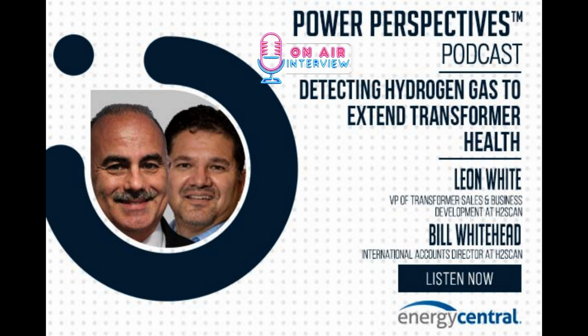Sure. So from an asset management standpoint, as you indicated earlier, transformers have gotten more expensive in recent years, doubling in price in just the last few years, and lead times on many transformers today are 2 to 3 years. And so that's increasing the criticality of the existing transformer fleet, since you want to take care of the assets you have and hopefully not have to replace them. And so from a safety standpoint, historically, utilities will take oil samples on large transformers once a year.